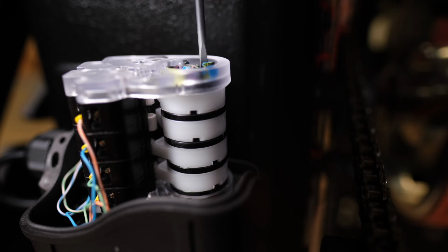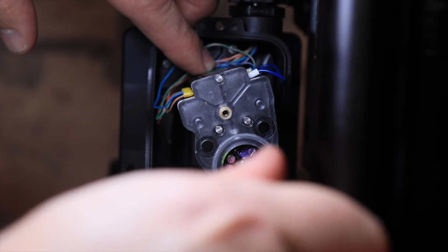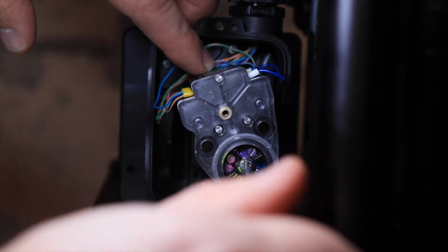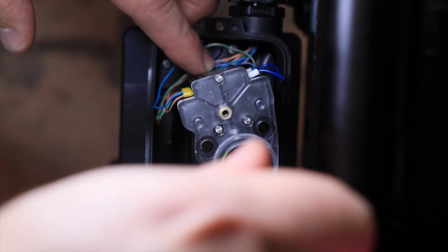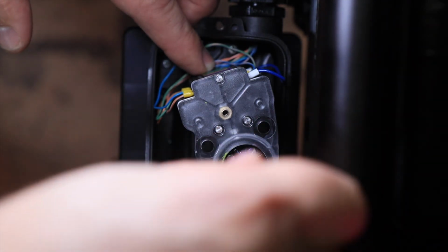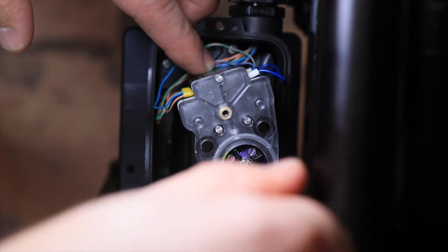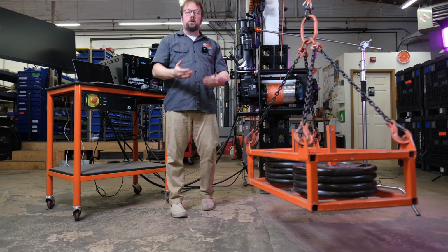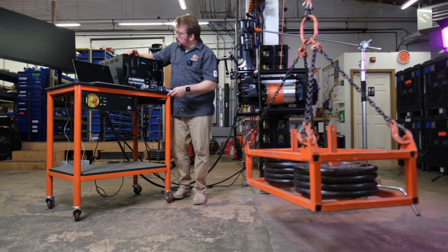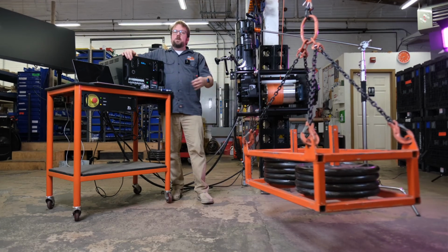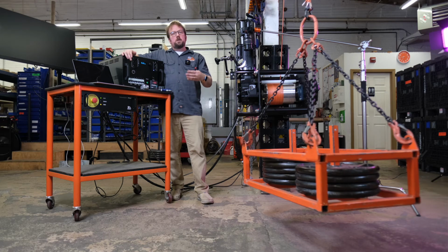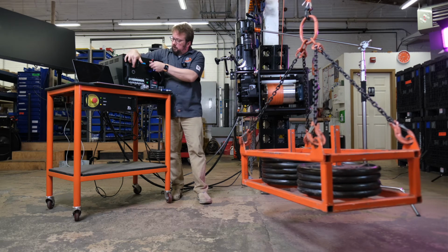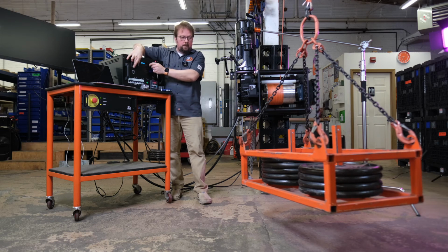And now I want to back off just a skosh. And the point here is that we want the ultimate limit to be close to the reverse initial limit, but we don't want to hit the ultimate limit first. We want to hit initial first and then ultimate. So we can't normally drive past the initial limit, which makes it hard to check the ultimate. But if I override the reverse initial, now I can go down into the ultimate.